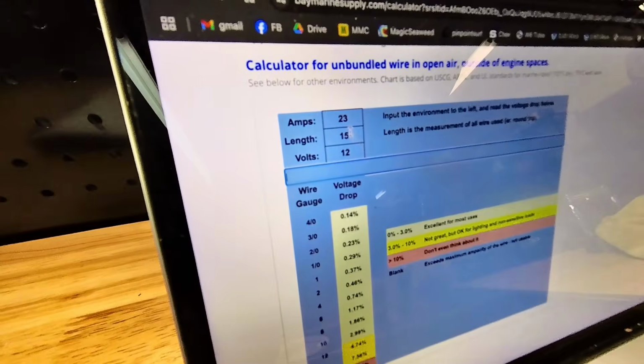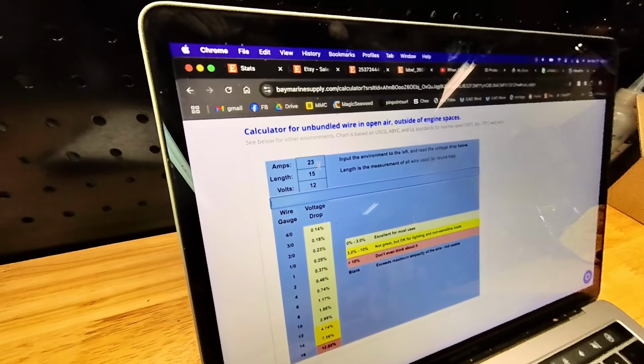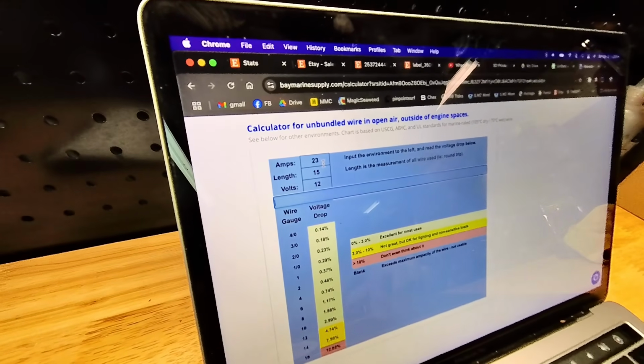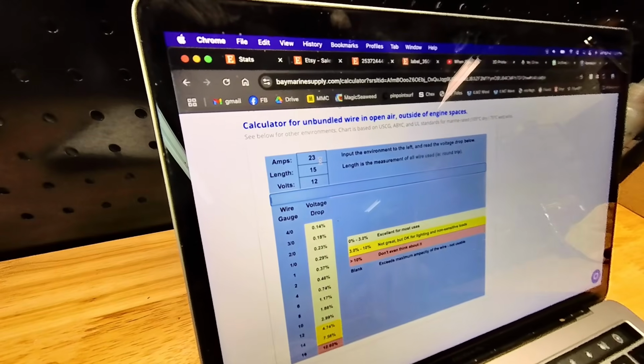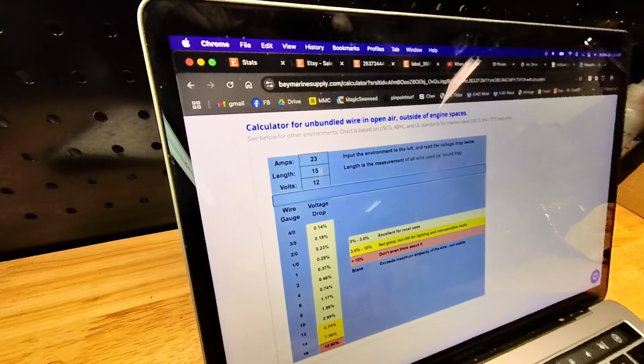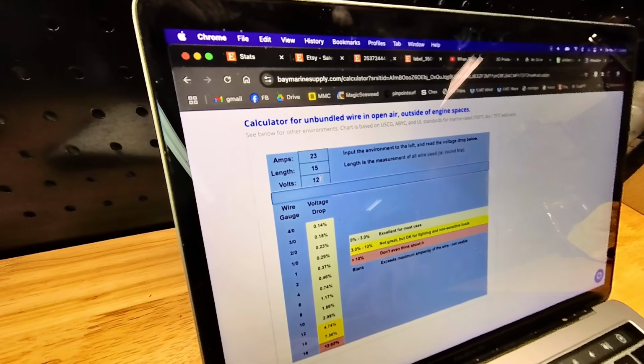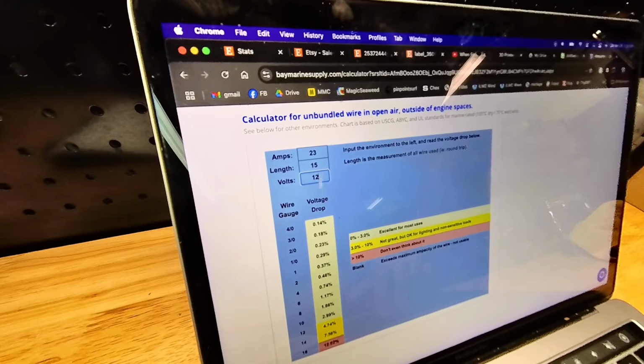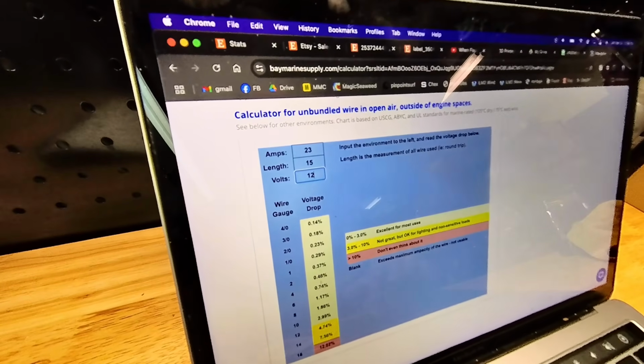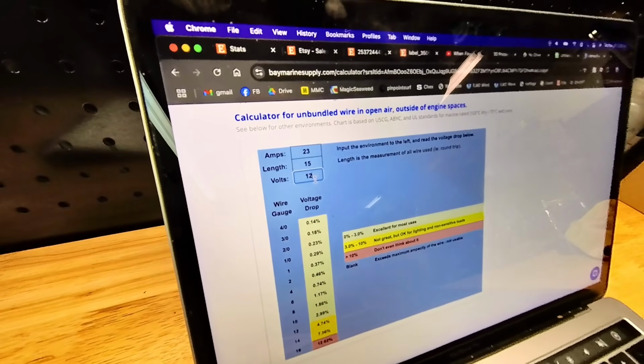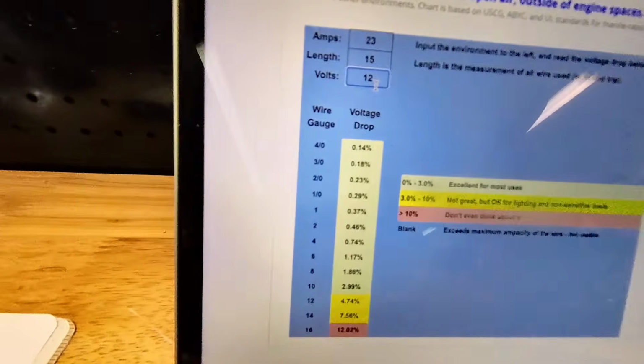These are all things we've already gathered. Amps is how much current we're going to pull, so I put in 23 as our peak load. Length of the wire is 15 feet. Then you throw in volts—I don't know why that's necessary since it calculates percent drop, but we'll use 12 volts as our nominal voltage. When you hit calculate, it spits out these values.